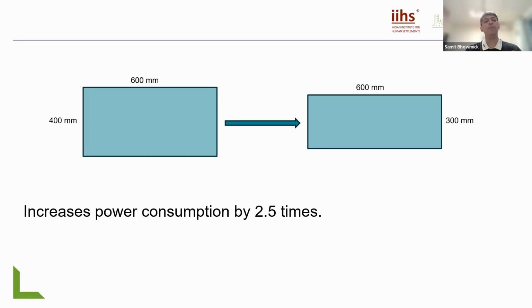We cannot simply compress ducts to accommodate a false ceiling height. You need to start looking at your building heights, and innovative ways of doing the false ceiling if you're thinking of a high performance building, because the impact is so much. Remember that the pressure drop is inversely proportional to the fifth power of diameter, so it's a very big impact, something we cannot neglect. It comes from common sense, but I very rarely find this applied in actual practice.